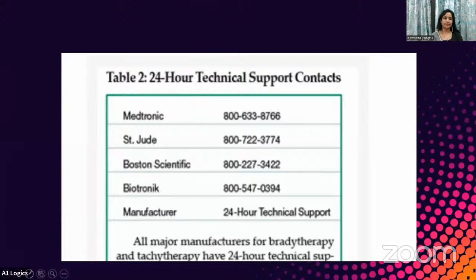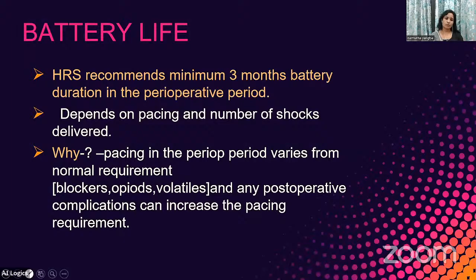Next, coming to the battery life. According to the Heart Rhythm Society, there should be a minimum of 3 months of battery life before taking up a patient for an elective surgery. Why is this important? Because the battery life is not the same for all devices. The lithium battery may last 5 to 8 years, but depending upon the type of device, the pacing rate, and how many shocks it is delivering per day, the battery life will start to reduce. Whenever you are taking up a patient for surgery, the pacing in the perioperative period is not the same as in normal time. Why? Because the patient will be exposed to drugs like opioids, beta blockers, or volatiles that can all act on the SA node and alter the pacing rate. They can increase the pacing rate, and any untoward complications in the postoperative period can increase the pacing requirement. That is why a minimum of 3 months of battery life should be there.